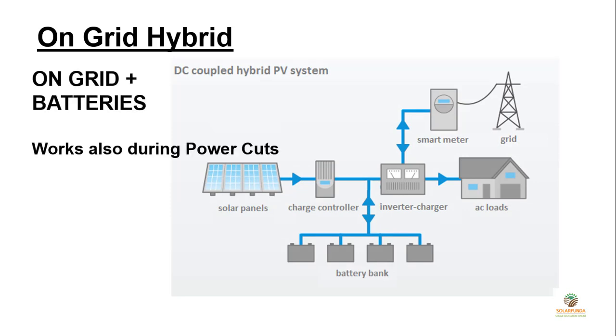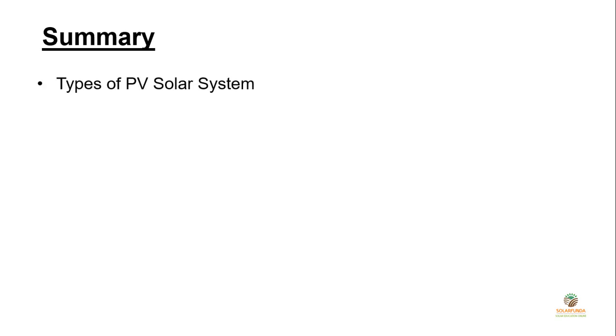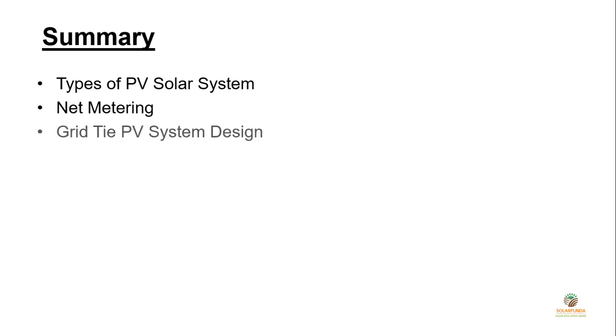Here is the on-grid hybrid system, where you can have battery backup. Normally, grid-tie systems do not work during power cuts due to the anti-islanding feature in the inverter. An on-grid hybrid system works even during power cuts because the battery is available. You can select batteries according to your required backup time, and batteries get charged by both solar and the grid — though this system is slightly costlier than a normal on-grid system. To summarize this session, we learned about types of solar PV systems, net metering, how to design a grid-tie PV system, the single line diagram, and the on-grid hybrid system.